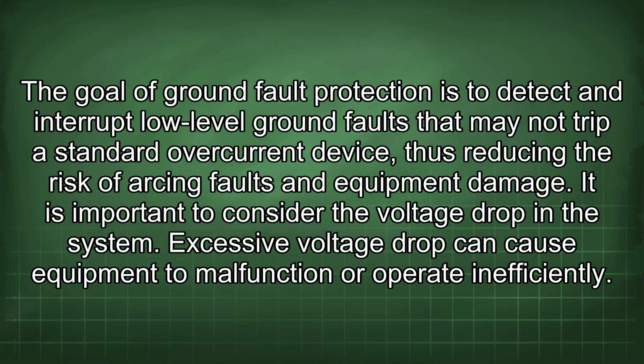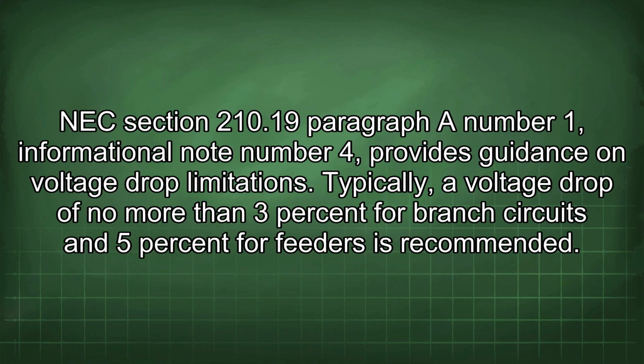thus reducing the risk of arcing faults and equipment damage. It is important to consider the voltage drop in the system. Excessive voltage drop can cause equipment to malfunction or operate inefficiently. NEC Section 210.19 Paragraph A Number 1, Informational Note Number 4, provides guidance on voltage drop limitations. Typically, a voltage drop of no more than 3% for branch circuits and 5% for feeders is recommended.